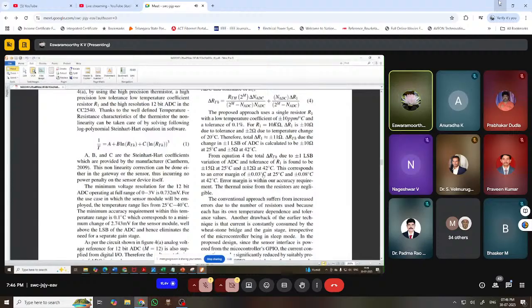So if it is measured, let's say 36 degrees Celsius, it may be 36.03, and otherwise 36, 35 means 35.03 or 34.97. So we achieved plus or minus 0.1 accuracy because the change is in another order, right?